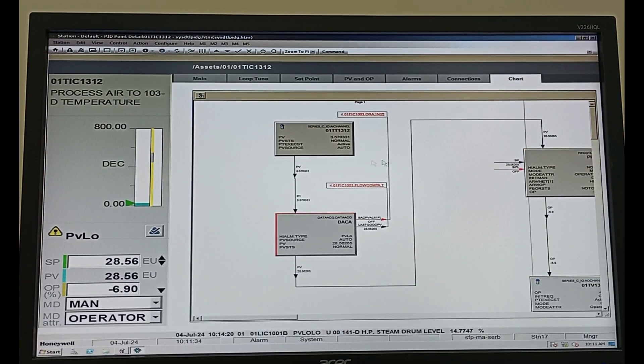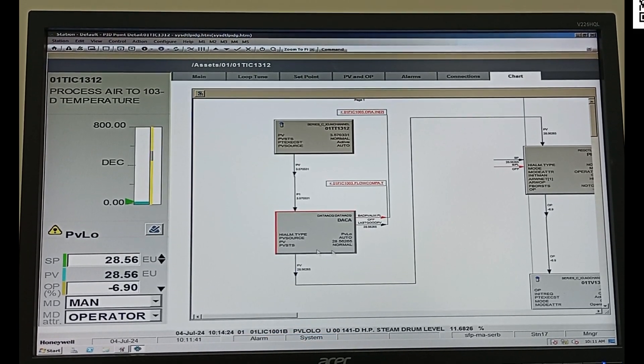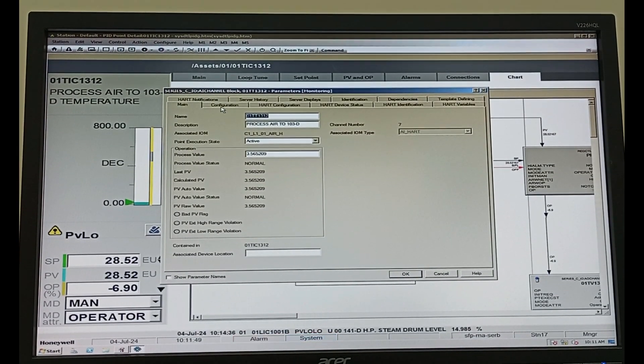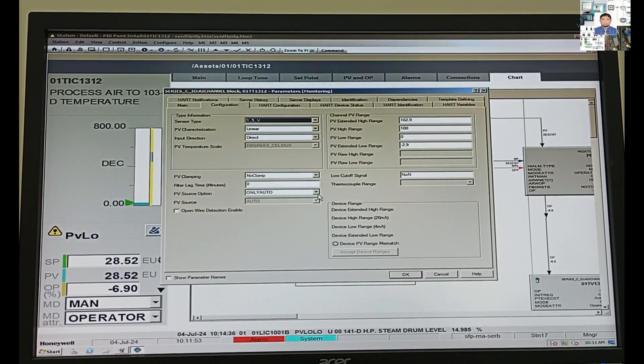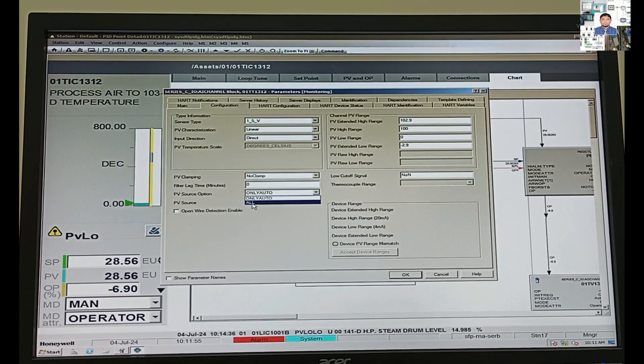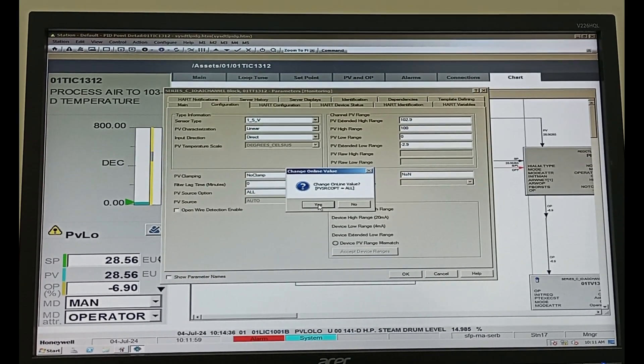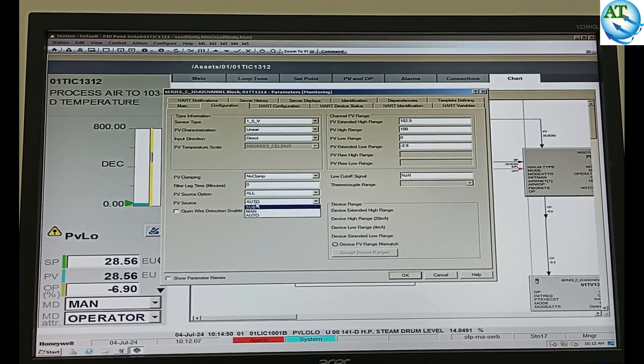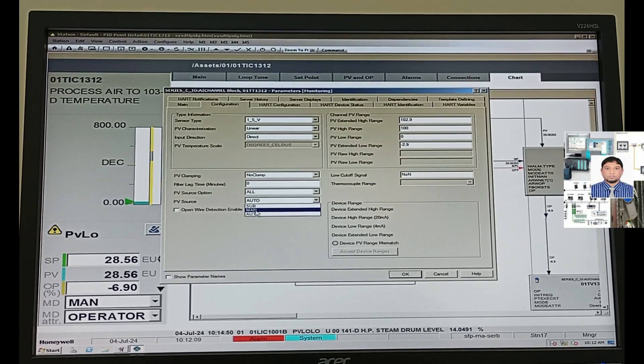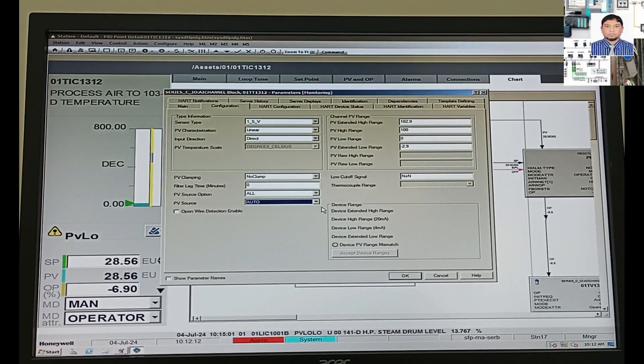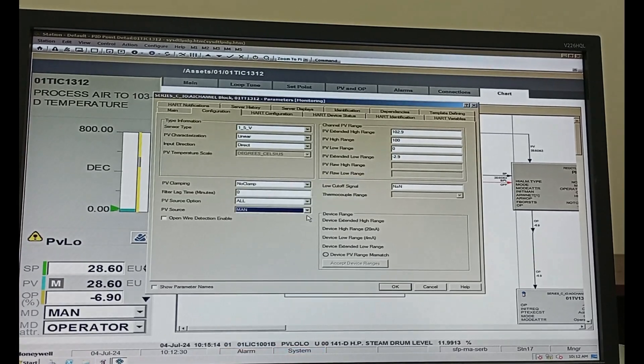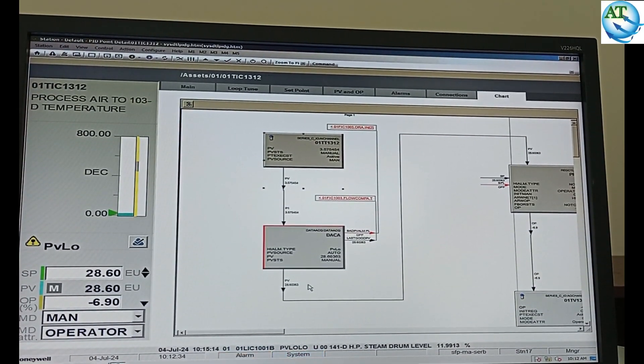With manager mode, you cannot force anything, you cannot change anything. So we go to the analog input block. First I show you how to make safe sourcing for the replacement. We go to the analog input block, go to configuration. Here, it is in only-auto mode. We can change this from only-auto to all. We go to yes. In the process mode, it gives a warning that the process is running — go online. Then when you see it go to all, you go to auto, and you have to change this to man mode. Go to man mode and press OK.